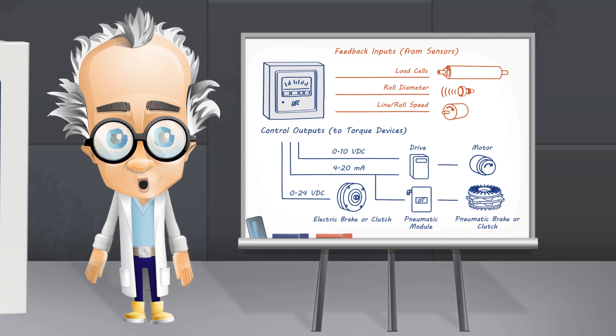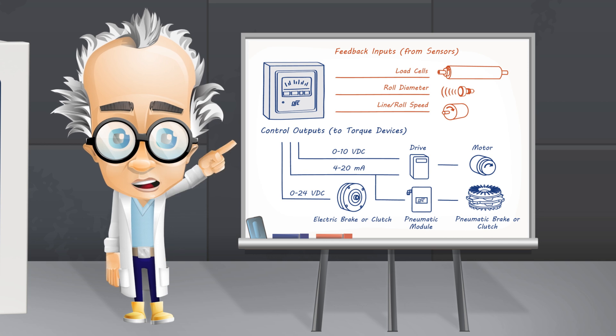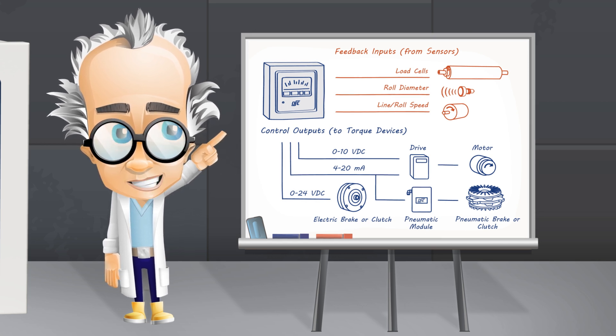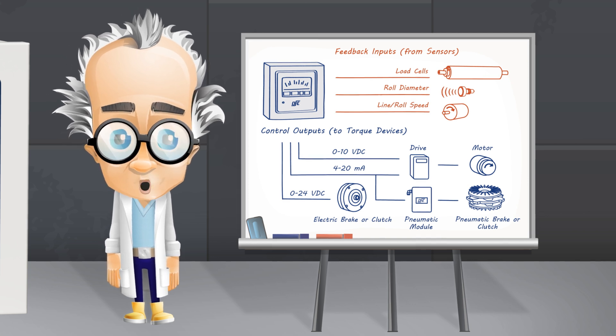Along with the web tension signal from the load cells, the controller can also utilize feedback from the line speed, roll speed, and roll diameter to enable additional performance features such as taper tension and acceleration compensation.